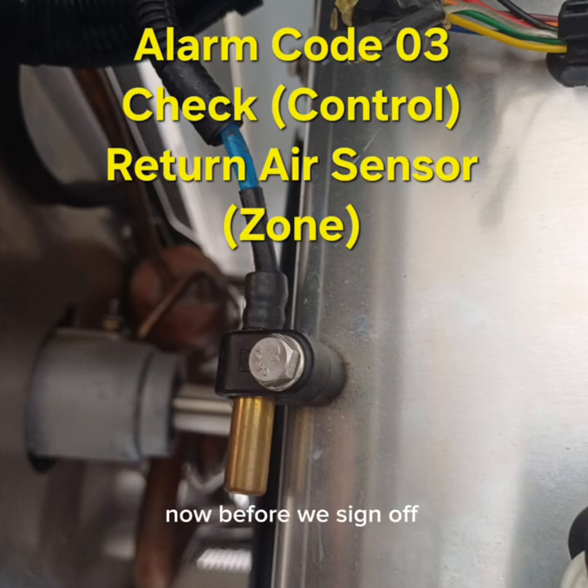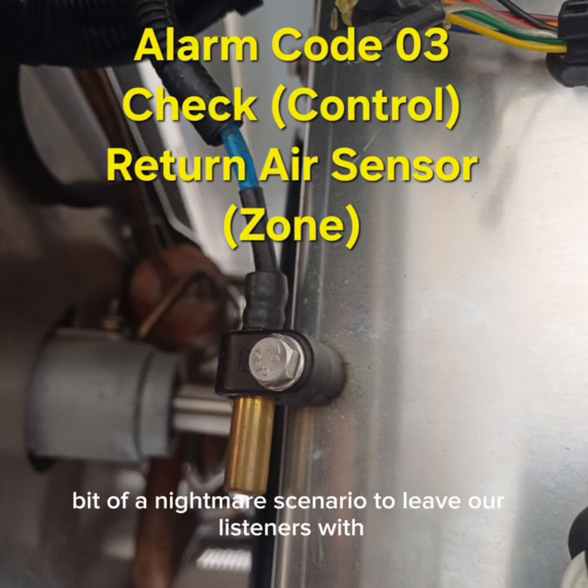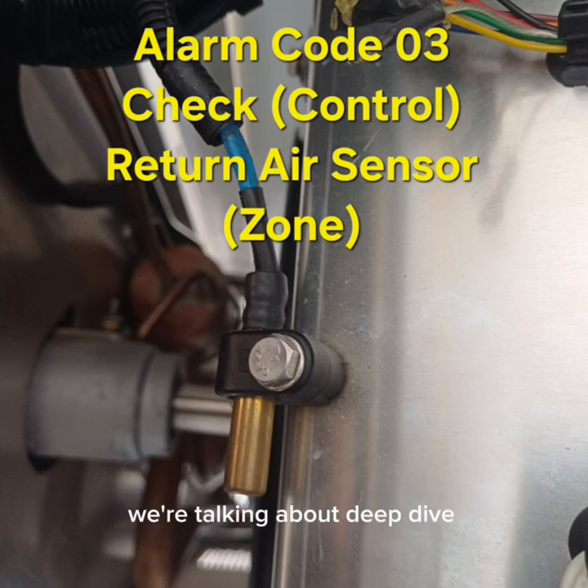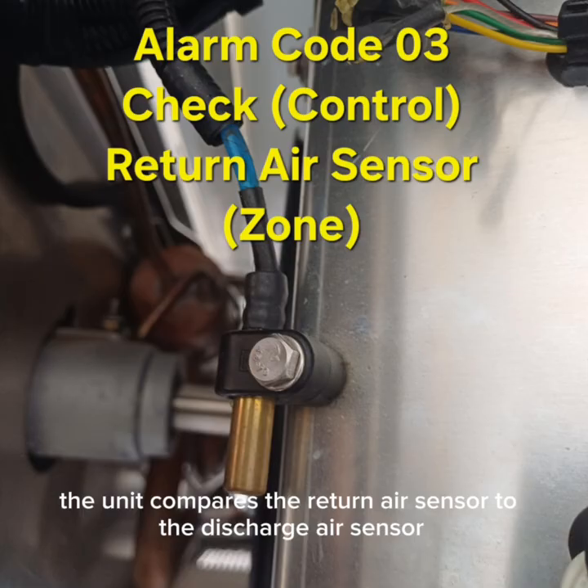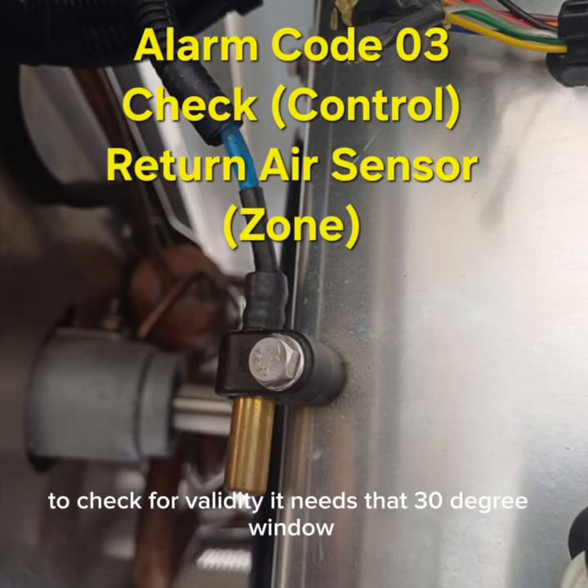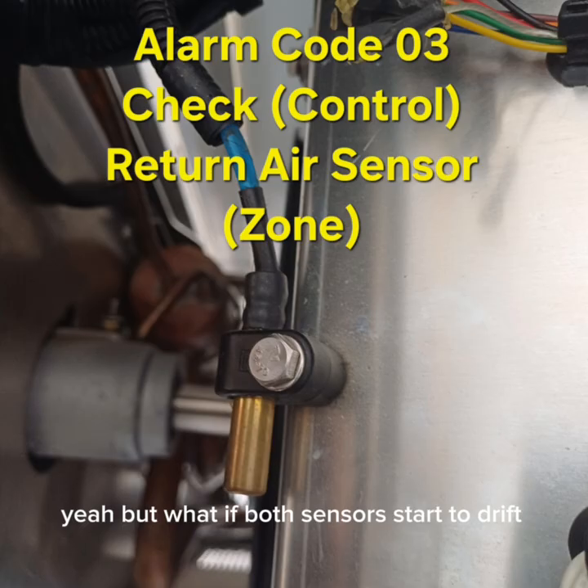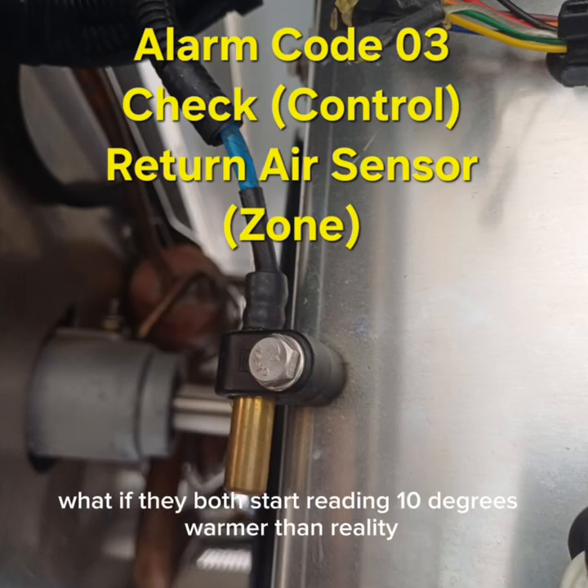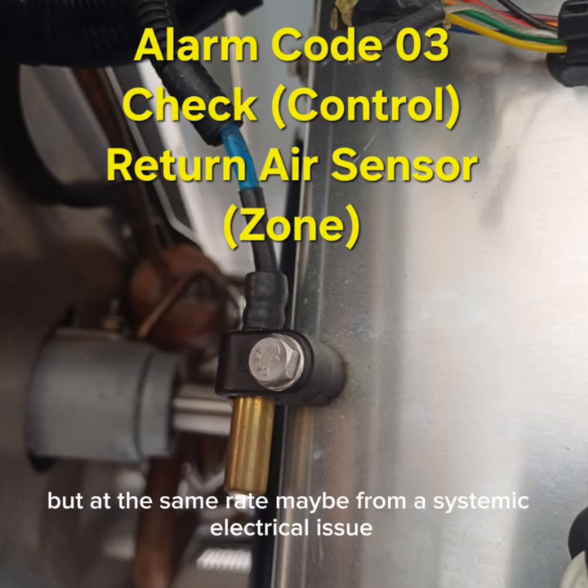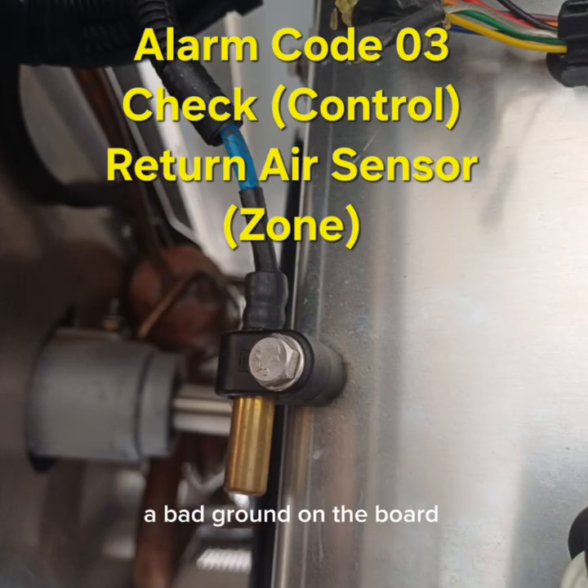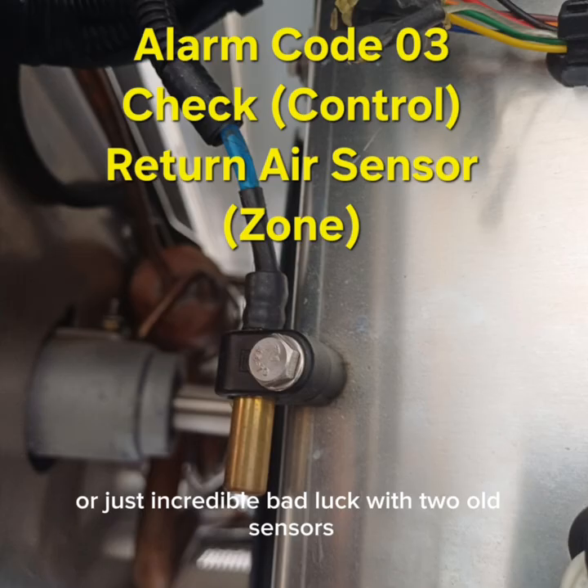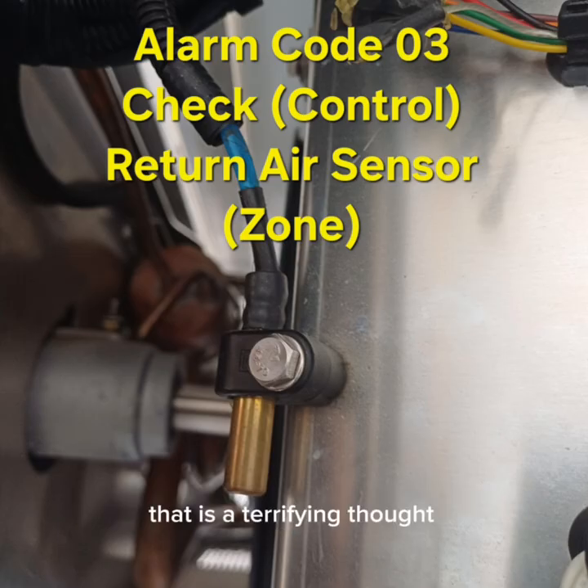Exactly. Now, before we sign off, I have a thought. Bit of a nightmare scenario to leave our listeners with. We're talking about deep dives, so let's go to the bottom of the ocean on this one. Well, let's hear it. We know the unit compares the return air sensor to the discharge air sensor to check for validity. It needs that 30-degree window. Yeah. But what if both sensors start to drift? What if they both start reading 10 degrees warmer than reality, but at the same rate? Maybe from a systemic electrical issue, a bad ground on the board, or just incredible bad luck with two old sensors. That is a terrifying thought.